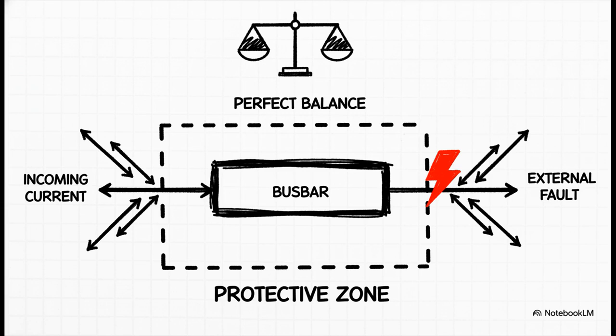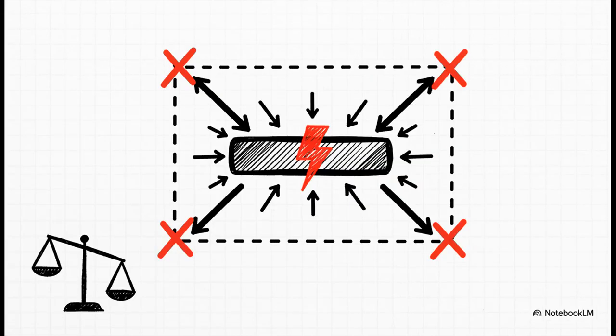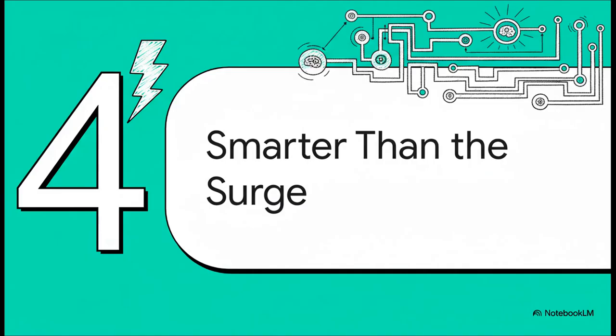Okay, let's walk through this. Scenario 1. Imagine a fault happens on a power line way outside the busbar zone. A ton of current is going to flow in through the bus, but then it's going to flow right back out towards that fault. So the total in equals the total out. The relays see perfect balance, they correctly figure out the problem is somewhere else, and they do absolutely nothing. They stand down. But now, look at this. A fault happens inside the zone, right on the busbar itself. Now current comes rushing in from all the connected lines, all feeding that short circuit. But almost nothing is flowing out. What goes in does not come out. The relays see this huge, undeniable imbalance, and in milliseconds, they give the command: instant shutdown, trip everything. It seems so simple, right?